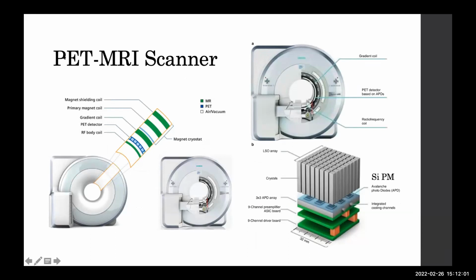It is a simultaneous acquisition of PET MR data. You can see in the cross-section image here. This is the PET MRI gantry, where there's a radio frequency body coil. This is the PET detectors, then again the gradient coil, and this is the magnet. So all this interposition together.